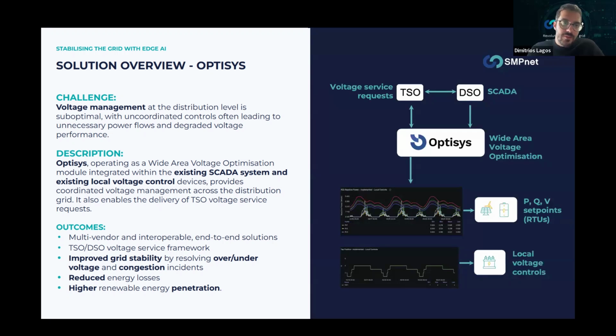So let's see here the solution overview of Optisys. As we said, voltage management at the distribution level is suboptimal, and you can have uncoordinated controls between the centralized solution and local controllers. Optisys comes to resolve this issue by operating as a wide area voltage optimization module for existing SCADA systems and coordinating with existing local controllers. In that way, it can provide voltage management to the distribution grid and deliver voltage service to the TSO. So it can be multi-vendor and interoperable with system operators' software.